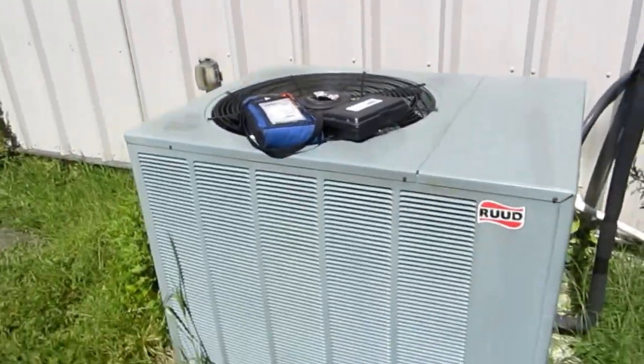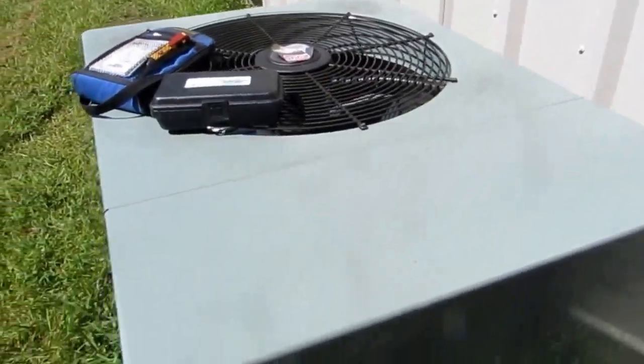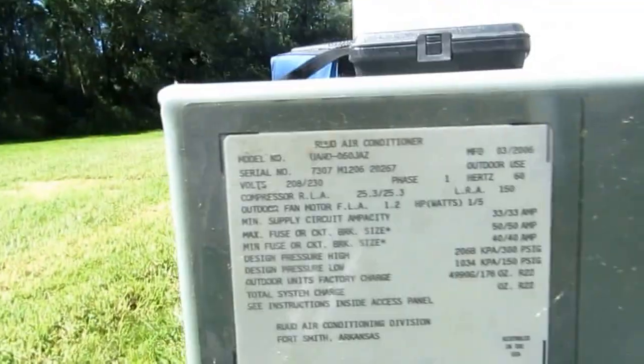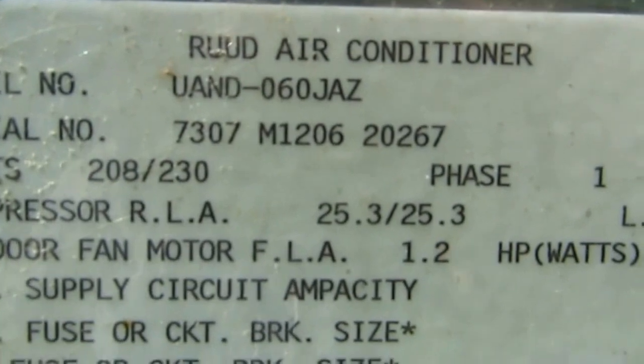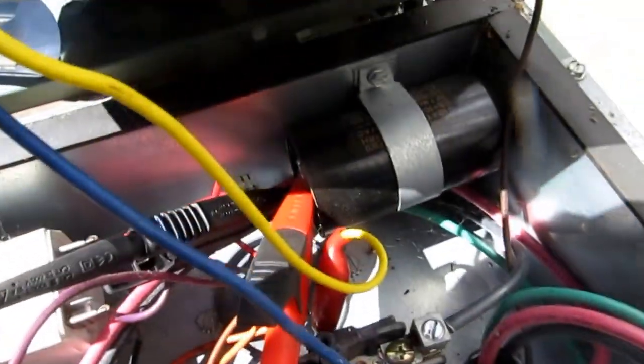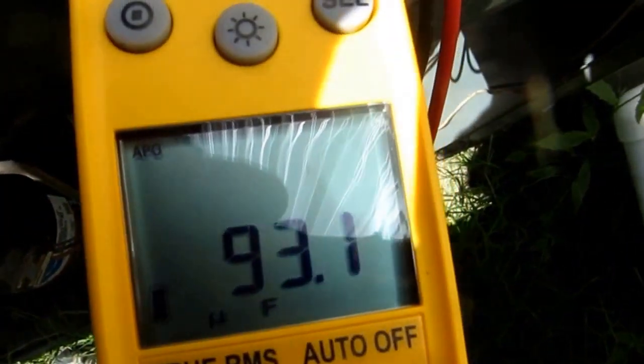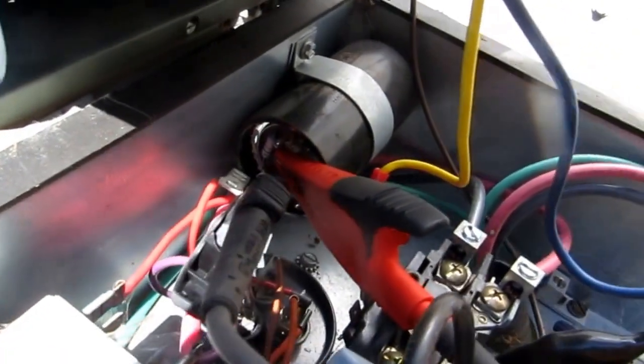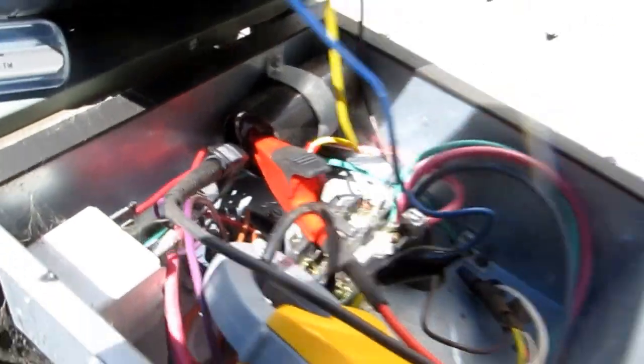Alright guys, I'm at this Ruud unit — I'm going to do a little testing with that meter. 5-ton, Ruud, 13 SEER. I'm checking that start capacitor — 93 microfarads. It's got that bleed resistor on there; you just put the meter on there and give it a couple of seconds and it starts reading.